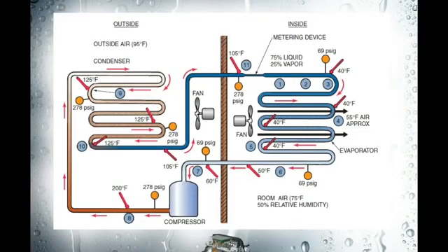In part one, we covered the first half of the refrigeration cycle, and that was on the suction side. Just as a quick review, this part of the refrigeration diagram here is where the refrigerant is in its saturated state, and we're adding heat to it and it is changing state but not changing temperature. And it follows its way down through the evaporator coil until it hits a certain point.